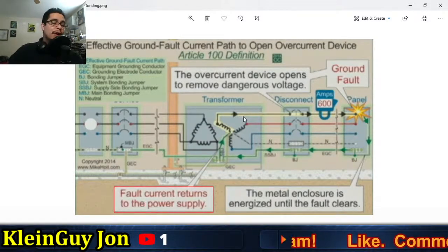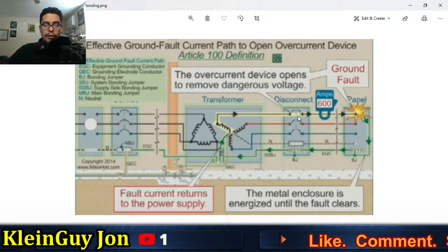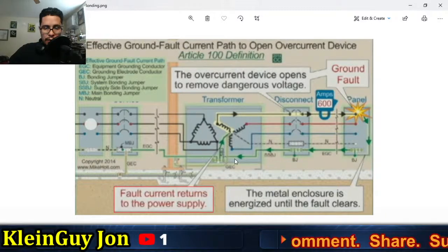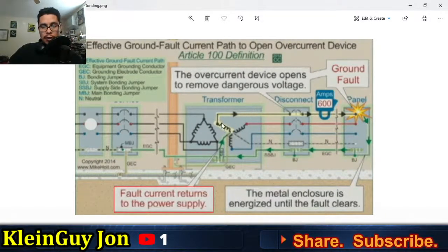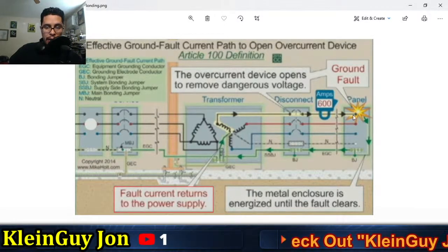sure we have an effective ground fault current path, where the electrons, in other words, you have to have a low impedance. In a structural building or in a constructed structure, you need to have a low impedance path from the point of the fault back to the source. And then your breaker, and what happens?